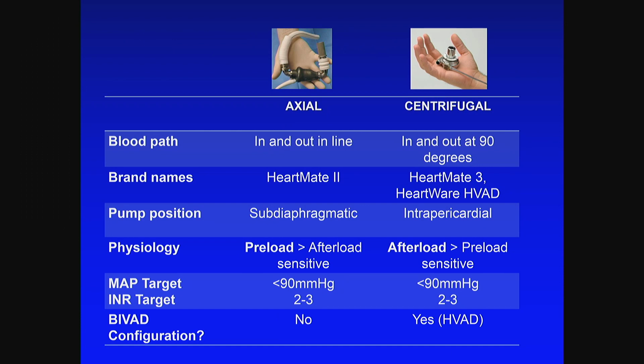So to review these two different pump profiles, the axial flow pumps, blood moves in and out of the pump in a straight line. An example is the HeartMate 2, whereas the centrifugal flow pump, blood moves in and out of the pump at a 90-degree angle. And these current pumps are the HeartMate 3 and the HVAD, which represent the most widespread devices in current use.